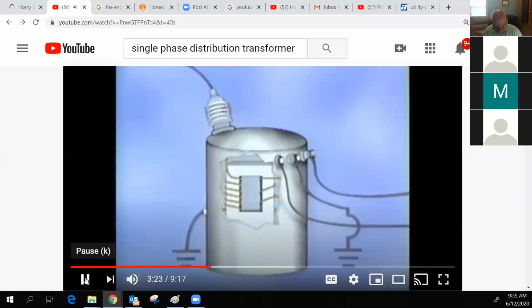You can recognize this type of transformer by the cylindrical housing, a large primary bushing on the top of the housing, and three secondary bushings on the side of the housing. This illustration is similar to the kinds of transformers you see on many overhead distribution systems. Both the primary and secondary bushings insulate the transformer leads as they pass through the housing.